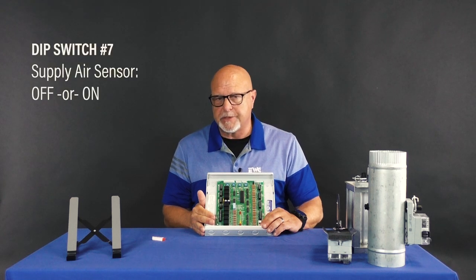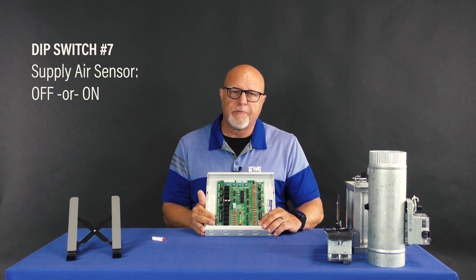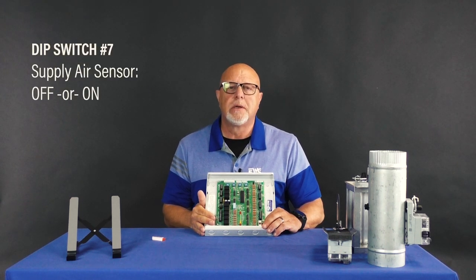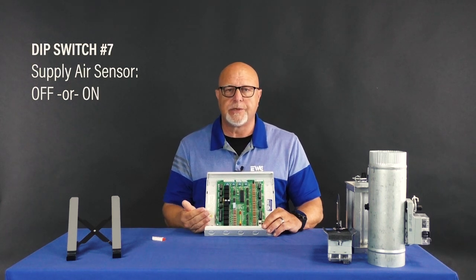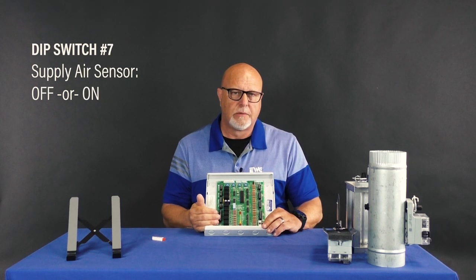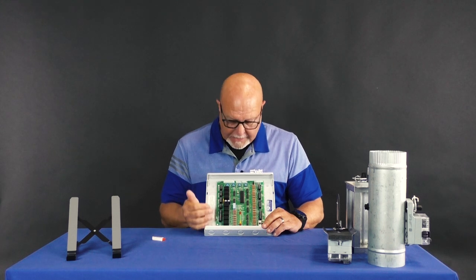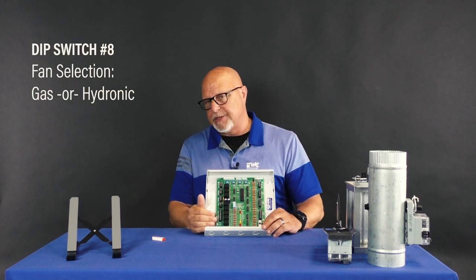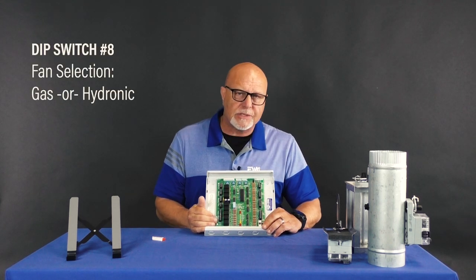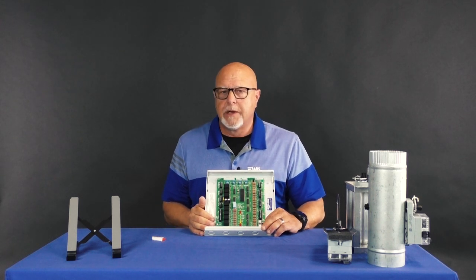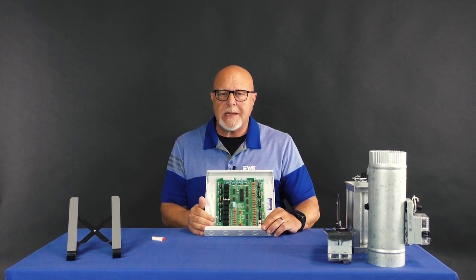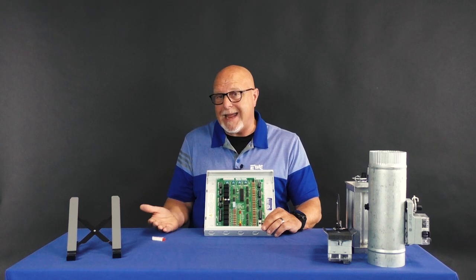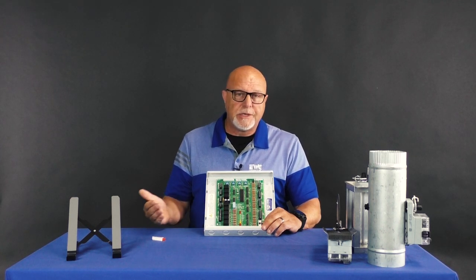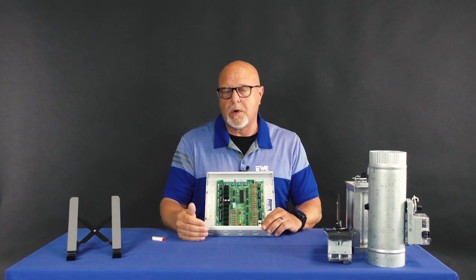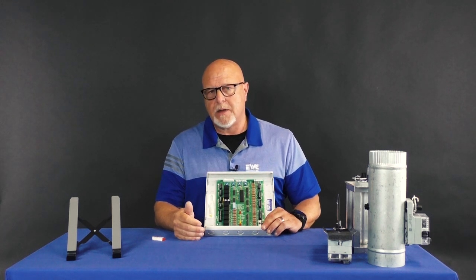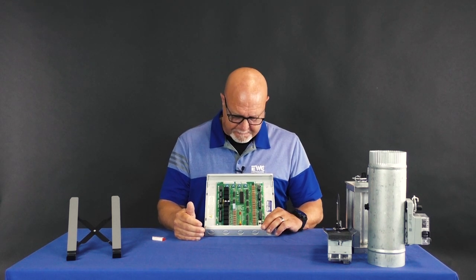The supply air sensor dip switch is going to come up from us in the off position. When you install the supply air sensor, we need you to turn that on. This last dip switch is your fan selection switch. It is either gas or hydro. It's going to come from us defaulted to the gas, meaning do you want the fan to delay until it turns on, or do you want the fan to come on immediately upon equipment startup?